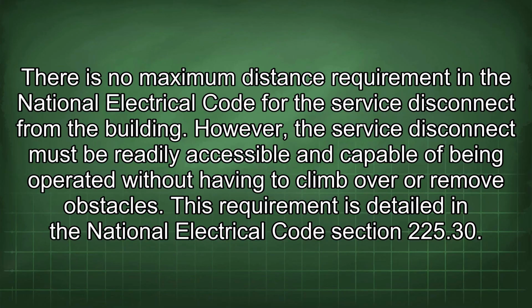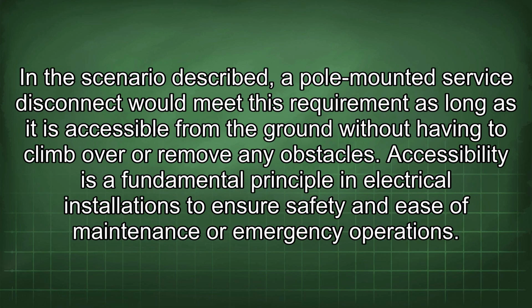There is no maximum distance requirement in the National Electrical Code for the service disconnect from the building. However, the service disconnect must be readily accessible and capable of being operated without having to climb over or remove obstacles. This requirement is detailed in the National Electrical Code section 225.30. In the scenario described, a pole-mounted service disconnect would meet this requirement as long as it is accessible from the ground without having to climb over or remove any obstacles.